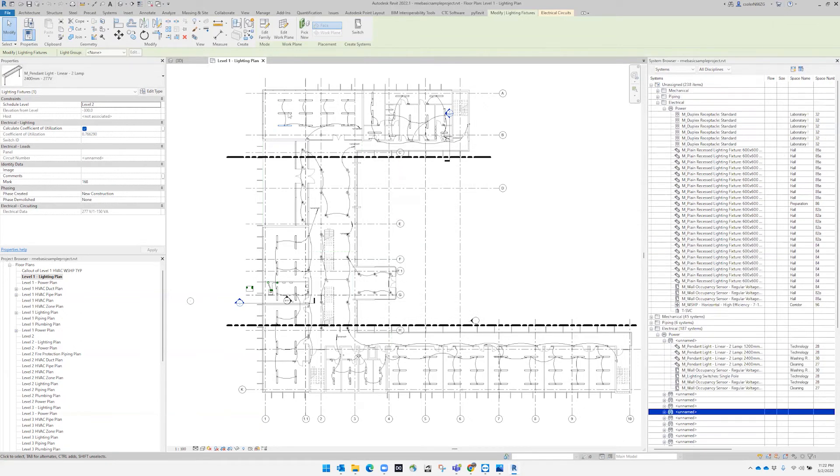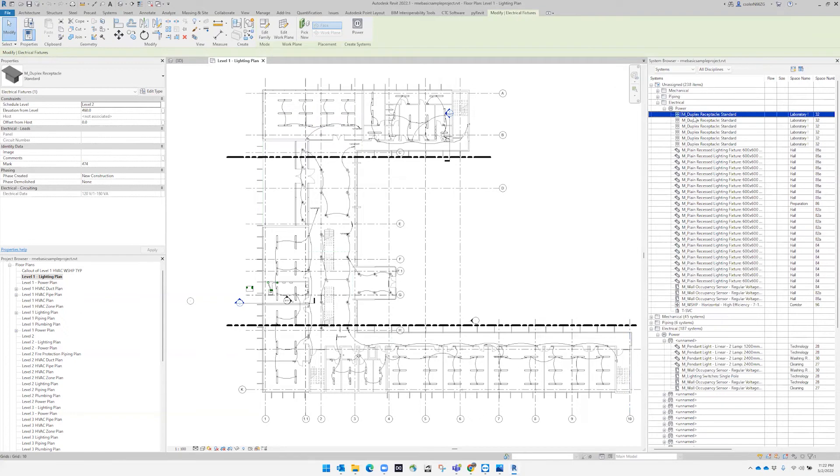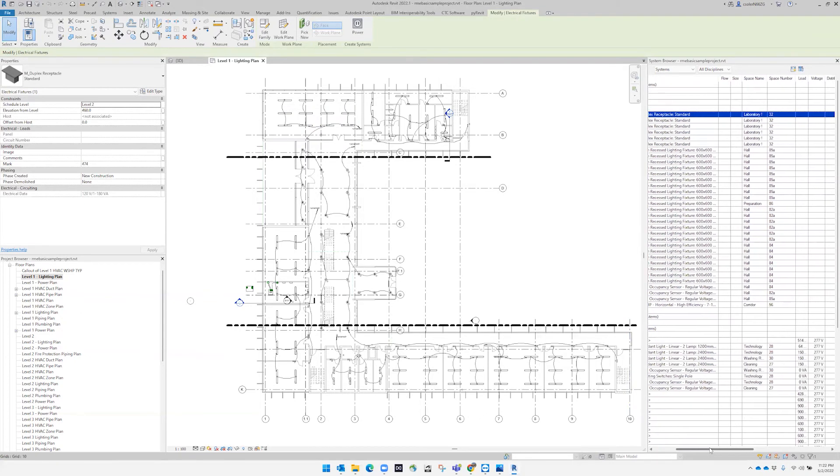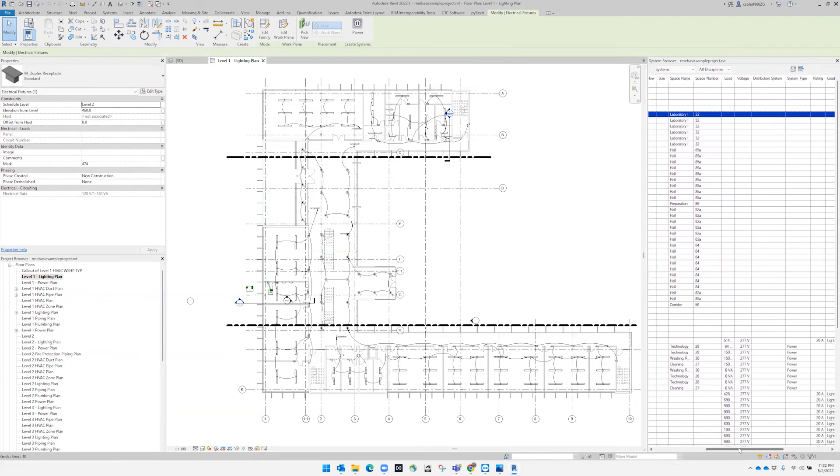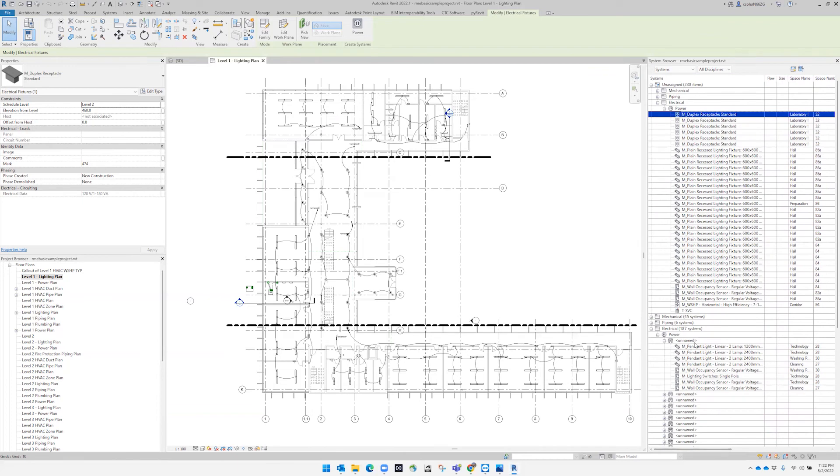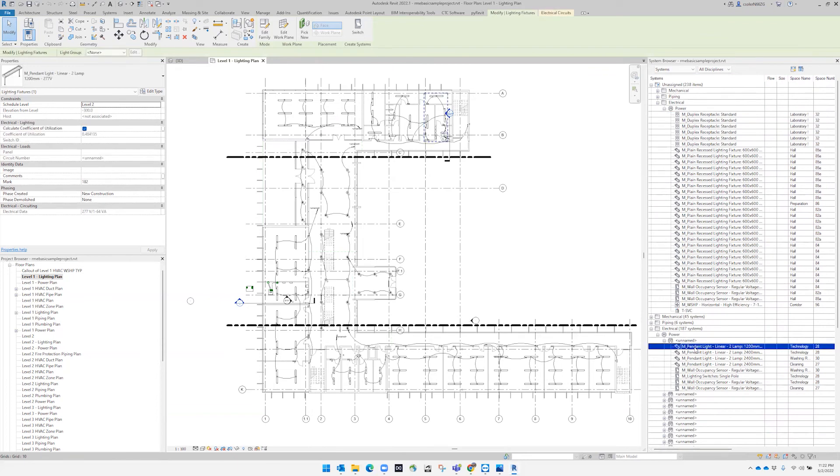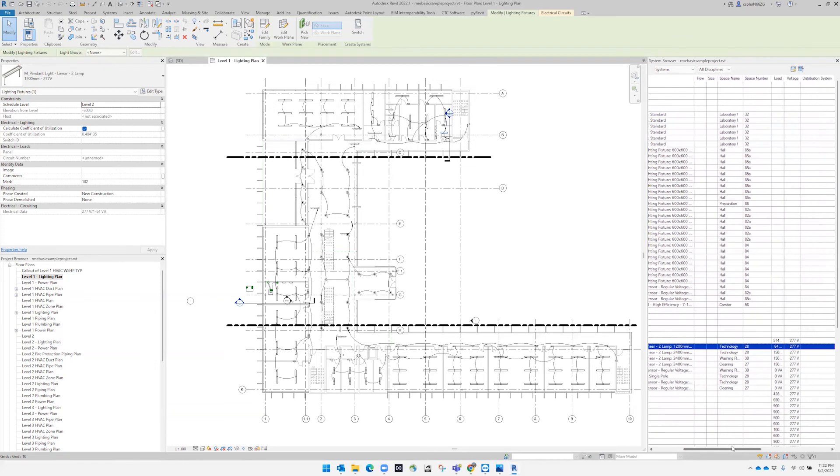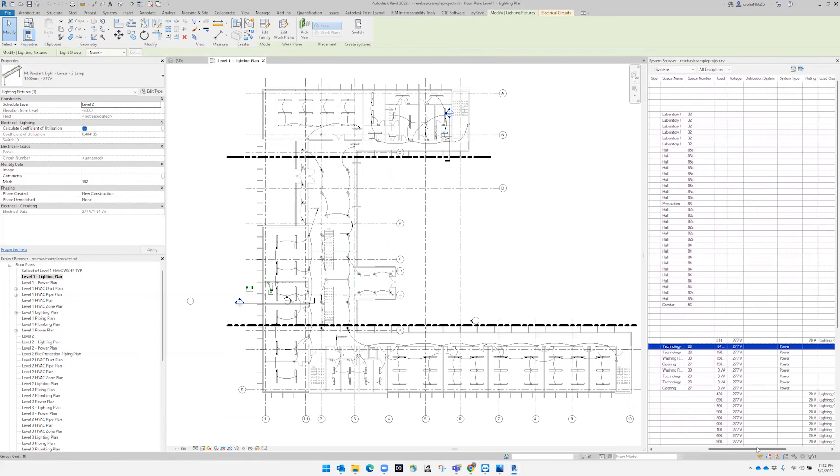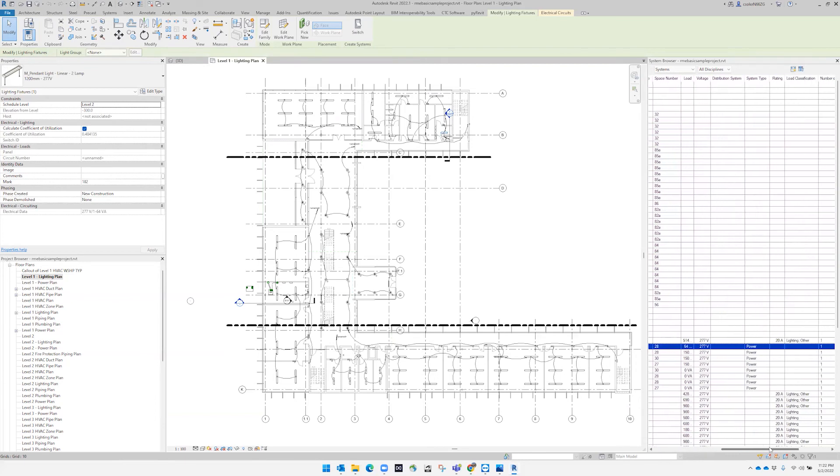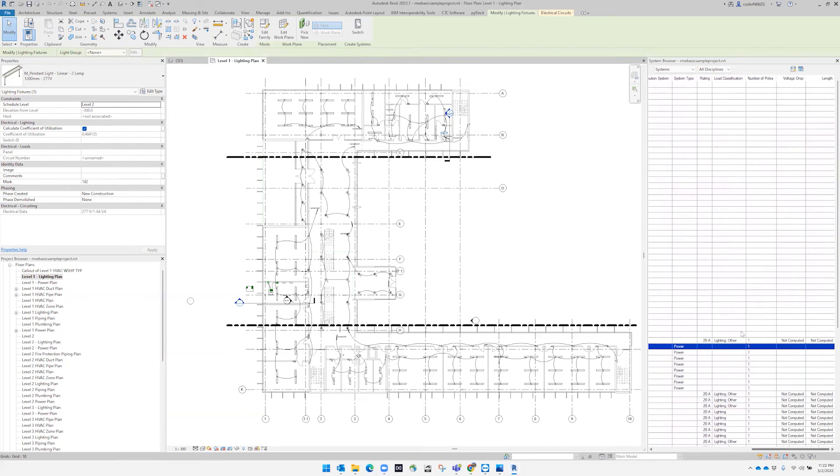So now, if we click this, for example, we can see the information: space number, where is it located. We can see all the device information. If you see this panel light that we highlighted, we can see the load, the voltage, the type of distribution system. The system browser is a really useful tool that Revit provides.